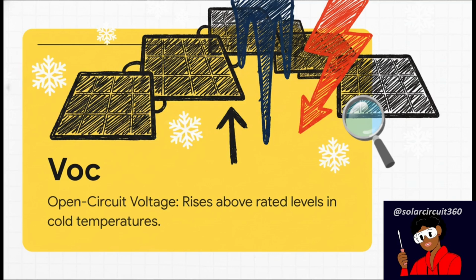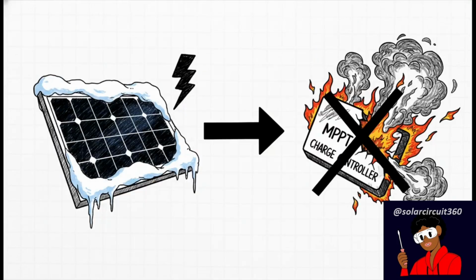And the crucial detail to remember is that as the temperature drops, a solar panel's voltage actually rises, and it can rise significantly above its rated levels. So sizing your series strings using only those standard summer Voc values, that is a total recipe for disaster on a cold winter morning. Because of that temperature spike, this specific mathematical check is literally a system-saving maneuver. Your cold weather Voc must absolutely remain strictly less than your MPPT's maximum input voltage. You have to verify this every single time.